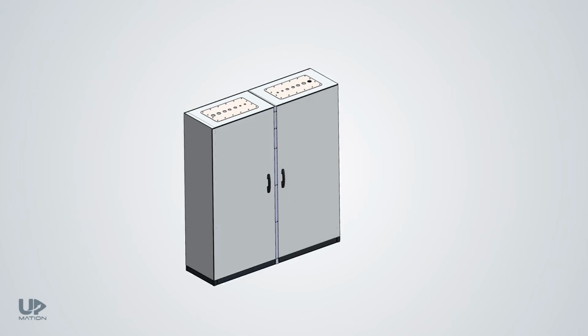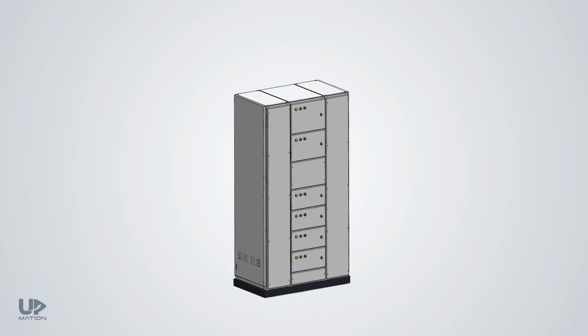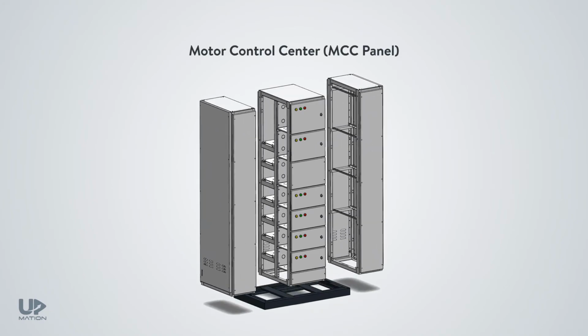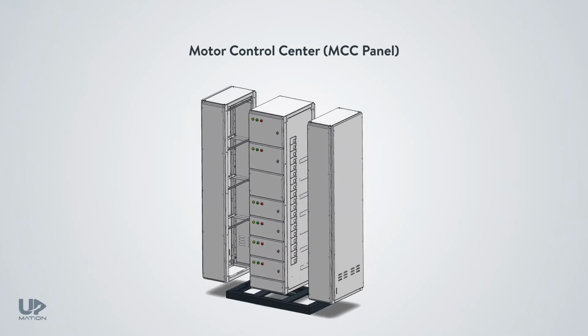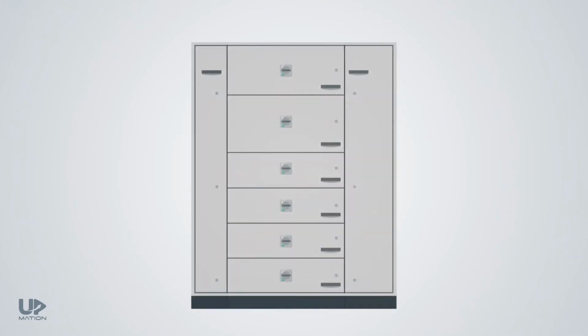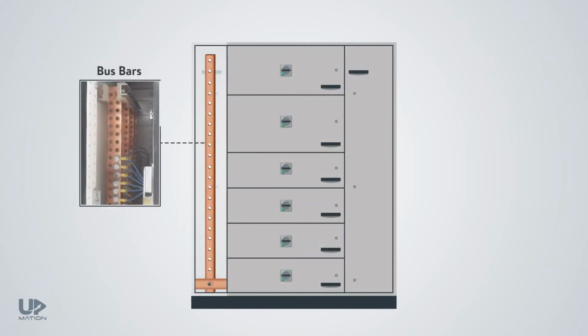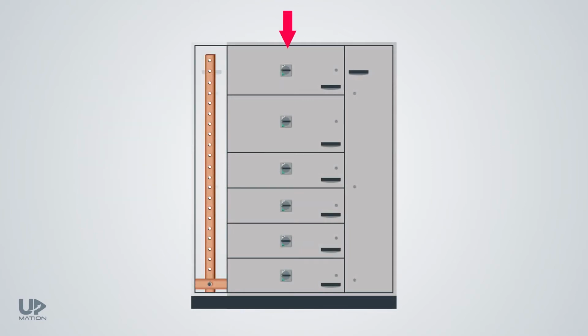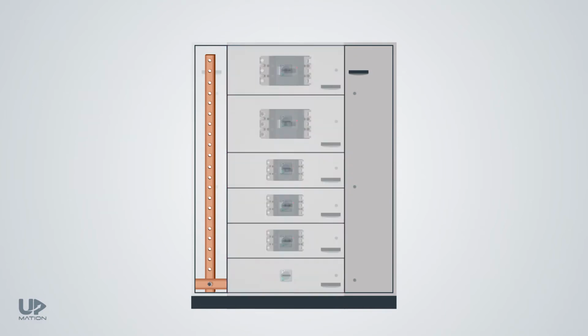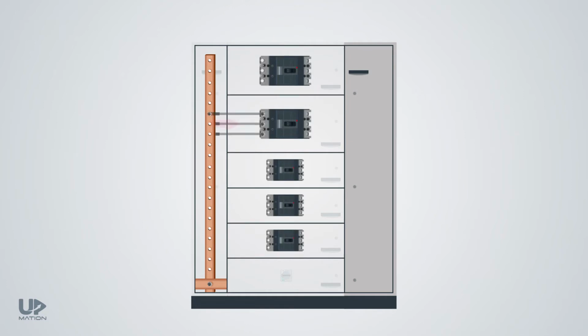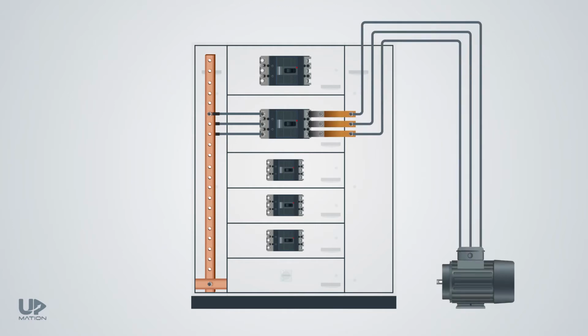Let me give you an example. Consider this motor control center or MCC panel. This panel has 3 separate compartments with different dimensions that are attached to each other. The left one contains the mains power bus bars. The middle enclosure consists of several other compartments, each one assigned to a circuit breaker of a specific electric motor. These circuit breakers take the power from the bus bars, and in the right-hand side compartment, the cables will be connected to the output of the circuit breakers and transfer the power to the electric motor terminal box.